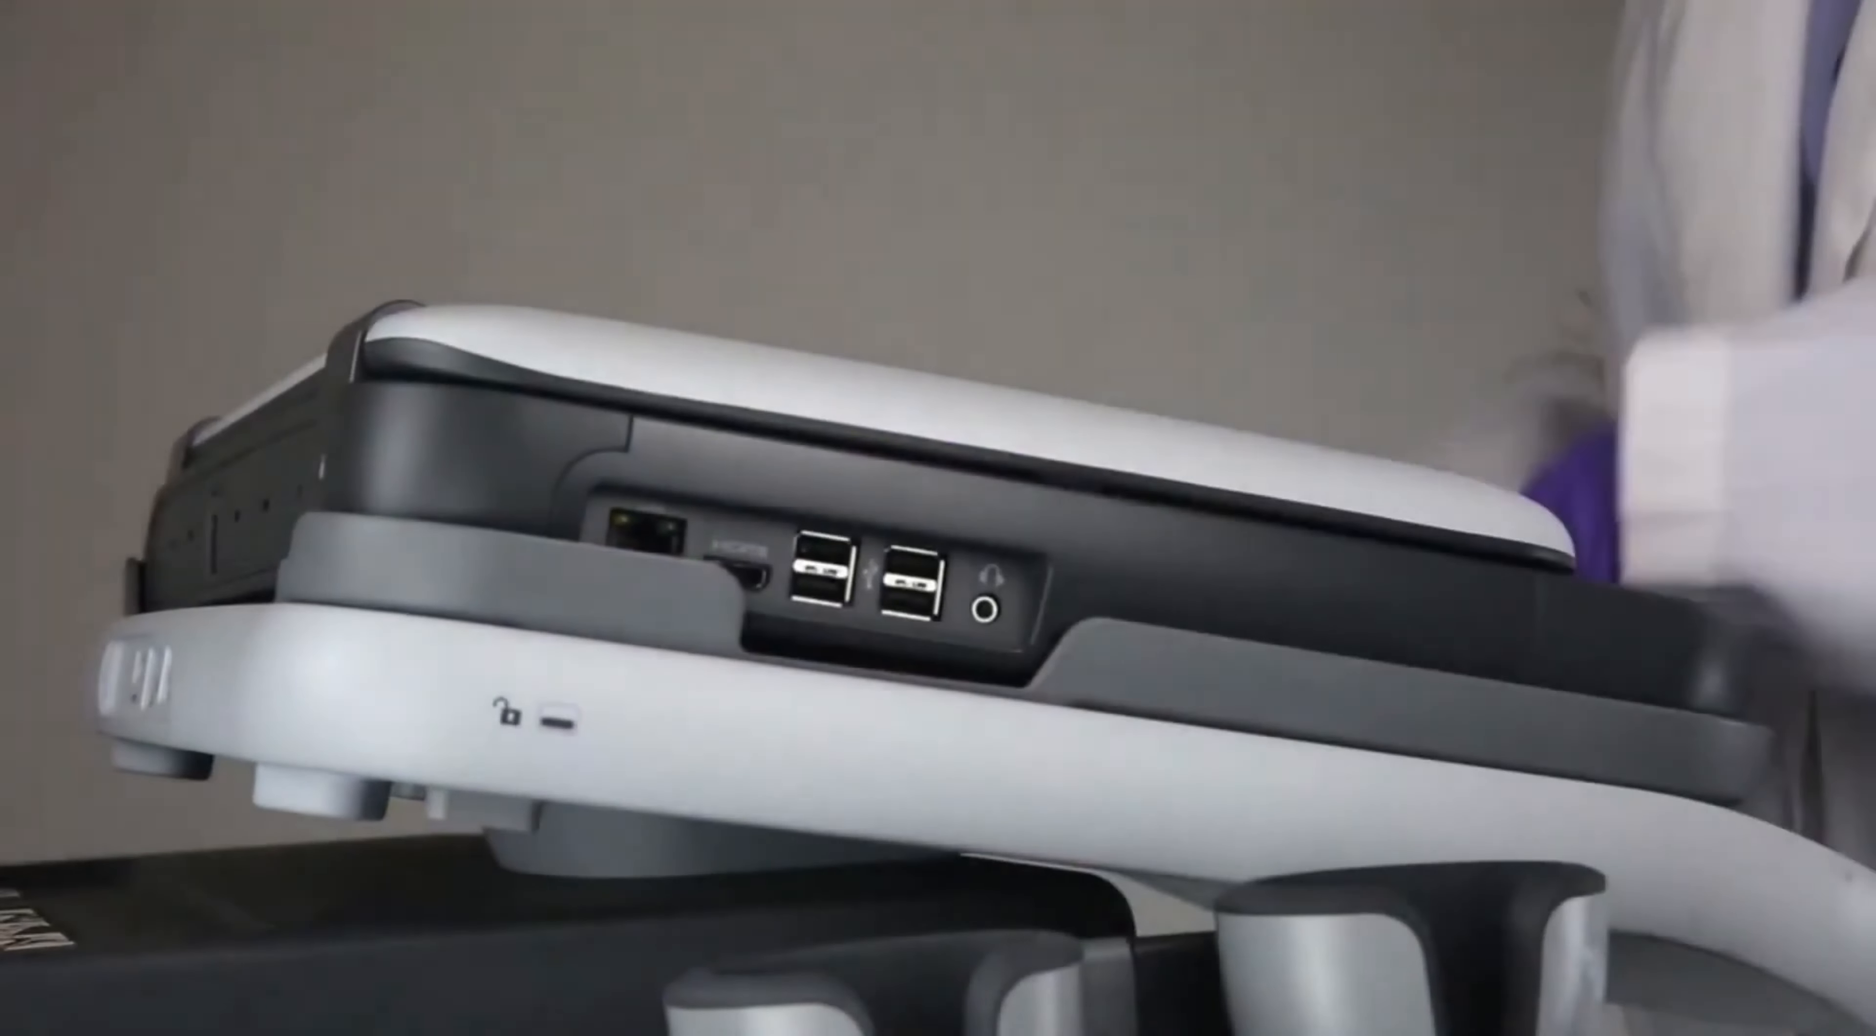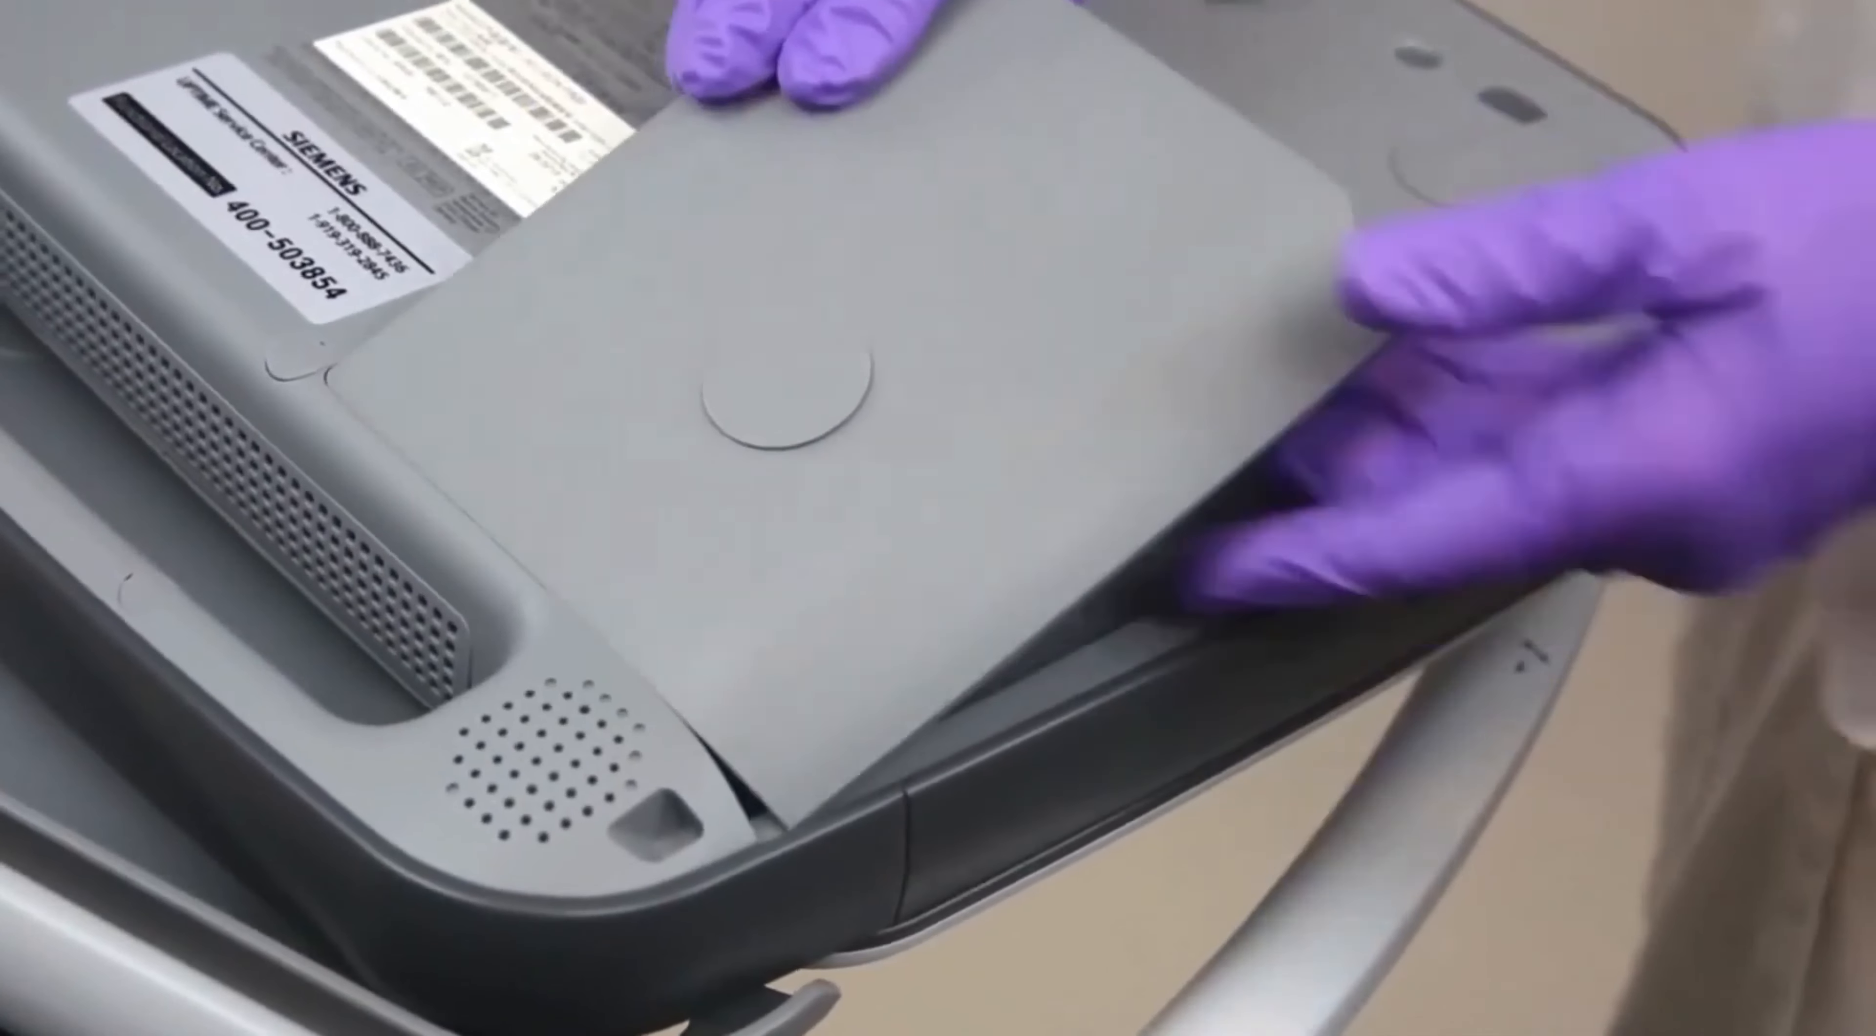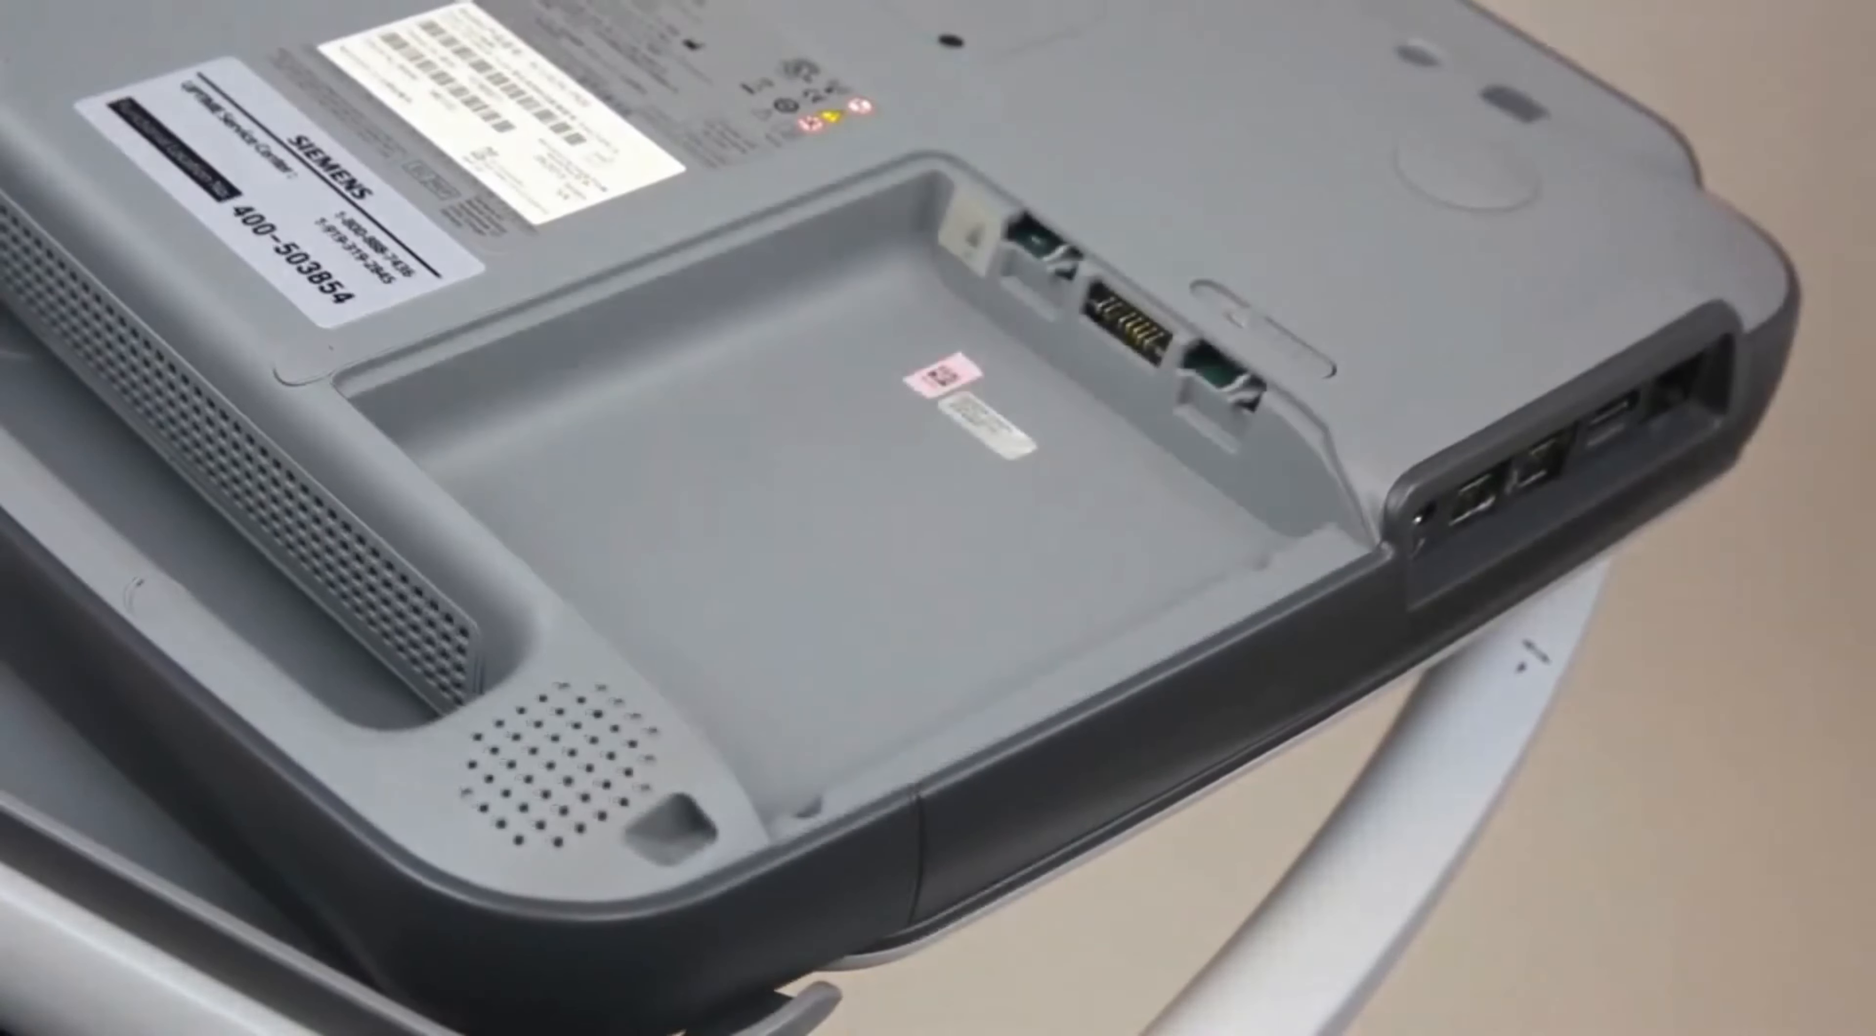To remove the battery, remove the Acuson P500 system from the smart cart. The battery is located under the Acuson P500 system. To remove the battery, slide the release until the battery pops out. Slide the battery into the slot and press until you hear a click to install the battery. It is recommended the battery be removed when the system is being cleaned, stored, or may be in a situation where it is hot, such as in a car.